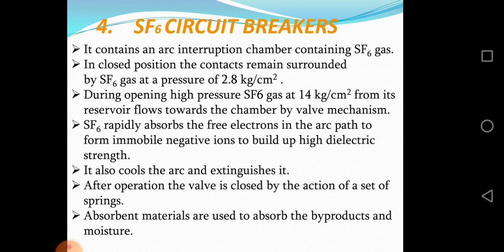SF6 rapidly absorbs the free electrons in the arc path to form immobile negative ions, building up high dielectric strength. It also cools the arc and extinguishes it. After operation, the valve is closed by the action of a set of springs. Absorbent materials are used to absorb byproducts and moisture. SF6 stands for sulfur hexafluoride.